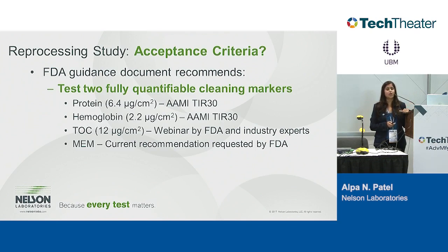Another thing that we're commonly seeing asked by the FDA is cytotoxicity testing after cleaning validations, to see if there's residual detergent left on those devices before they go to the next step. That is usually performed through a minimal essential media MEM test, which is a very simple, very easy test, and it only requires one device. But keep in mind that this is something that we are seeing recurring over and over again from the FDA.